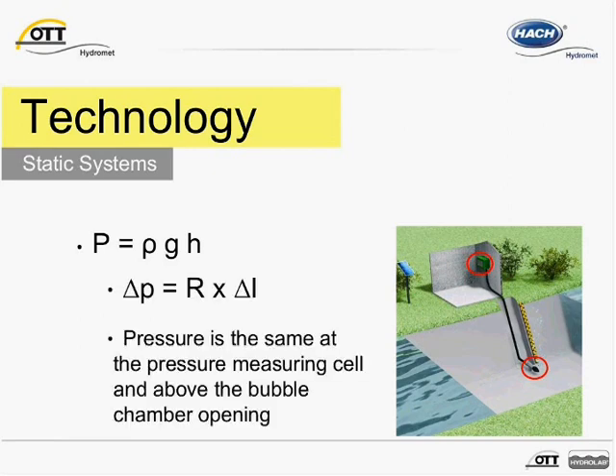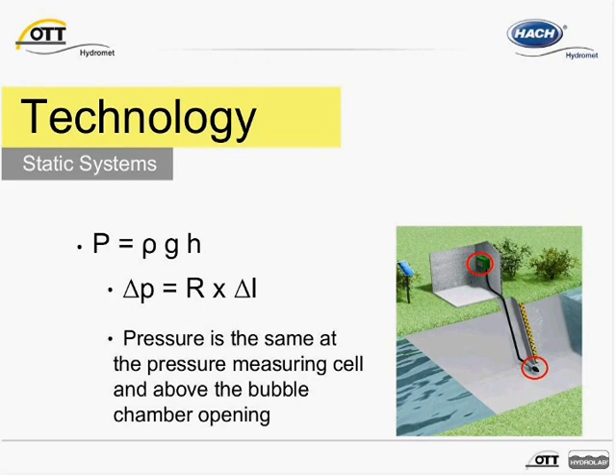The next equation looks at R, the resistance of the complete system, and this includes the pressure measurement cell, measurement tube, and bubble chamber. The resistance of the complete system times the change in air flow, indicated here as capital I, is used to calculate pressure at the measuring cell and at the measurement tube opening, shown here as capital P. With static systems, air flow and resistance are constant, where any changes in air flow are equal to zero. Therefore, changes in pressure are also equal to zero. In other words, static bubbler systems maintain the same pressure throughout the system. This means that the same pressure can be observed at the pressure measuring cell and at the orifice opening in the water.